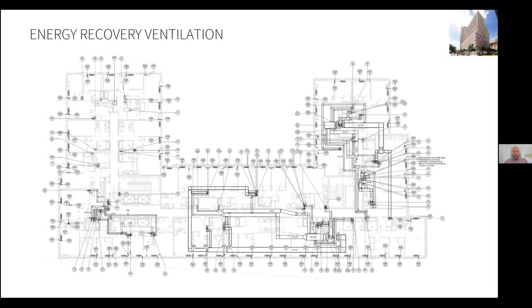So the other option for ERVs is a centralized system. On Cooper Park, we are using a centralized system, and the decision was initially made for this system based on aesthetics. The ability to remove the louvers from the facade helped in our additional goal of meeting Passive House standards and reducing penetrations. Cost implications raised by the GC on board resulted in us doing an analysis of the cost to increase floor-to-floor heights so that horizontal ducts in a unitized system allowed soffits to have a minimum ceiling height of 8 feet to provide the required habitable space below them. Moving the horizontal ducts and going with the centralized vertical system saved at least 4 inches, likely 8 inches per floor on 13 floors, reducing costs of the building materials from structure, facade, finishes, et cetera.